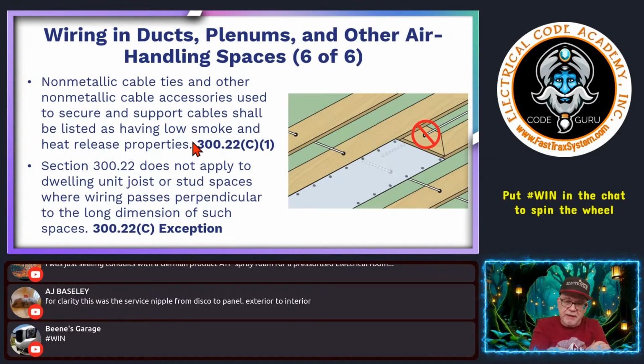Now, one of the key things under the exception is for dwellings, we're geared back towards dwellings a little bit. 300.22 does not apply to dwelling unit joist and stud spaces where the wiring passes perpendicular to the long dimension of such spaces.